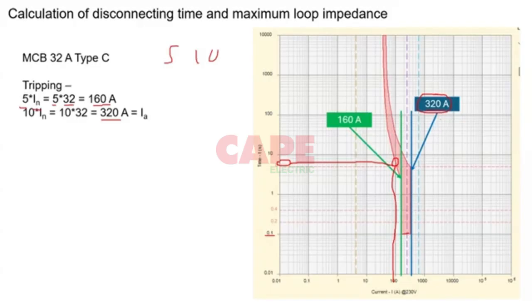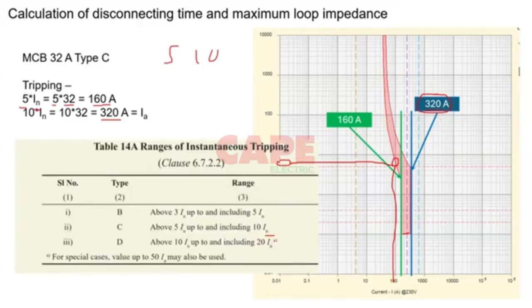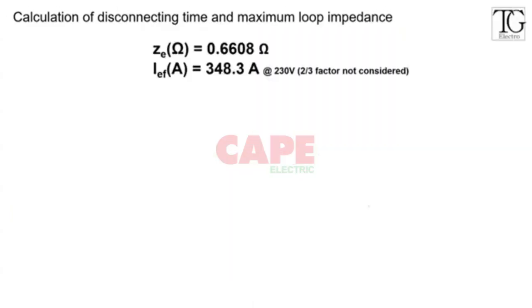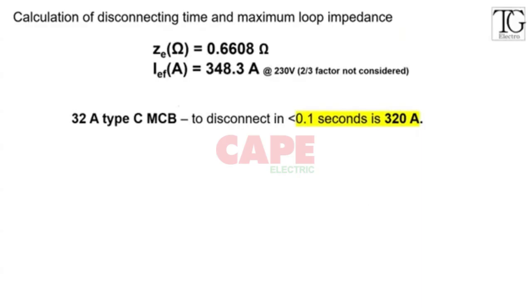Now, I'm not taking these values from somewhere else. This is all mentioned under the instantaneous trip. This is referred to in NEC also. In NEC, you can go to this clause or table 14A, where they have mentioned the tripping characteristics of MCBs. Now, for a 32 amp C-type MCB to trip within 0.1 seconds, you need 320 amps.